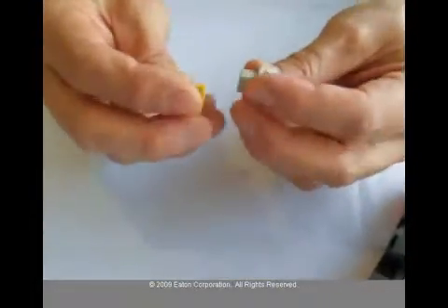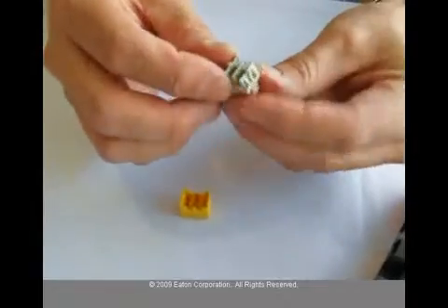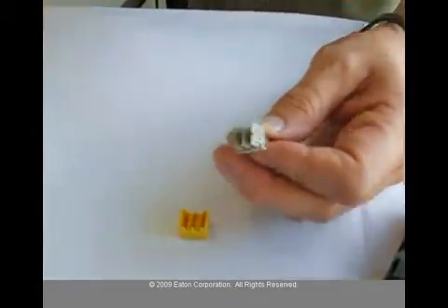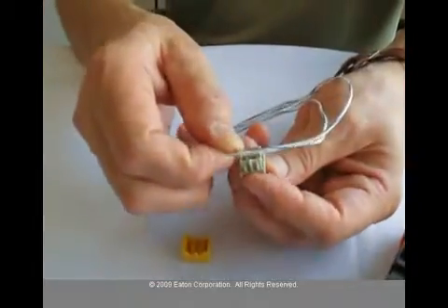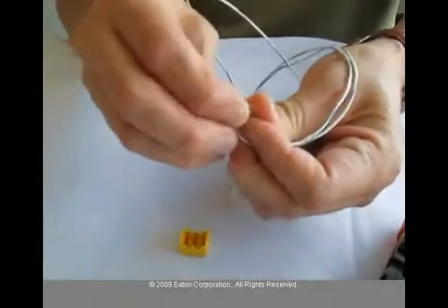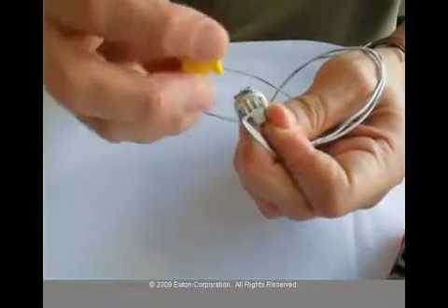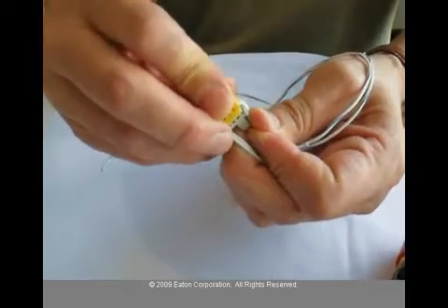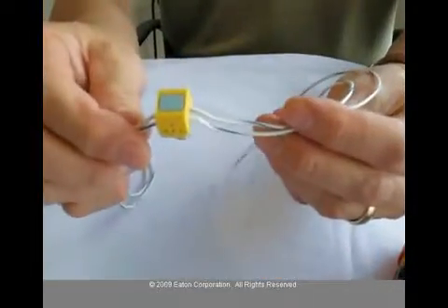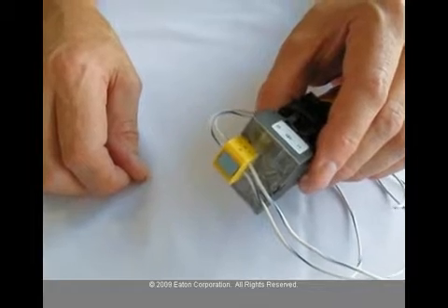Now, something else that comes with the adapter is an OSI connector. This OSI connector is an insulation displacement connector. So if you take two wires and put them in these grooves in the connector, hold them in place, and put the connector over the top, they make the connection for you. No screwdrivers or any other tools are necessary. Plug it into the unit and it's now on OSI.